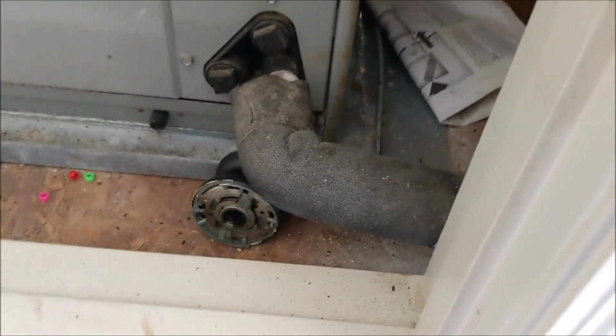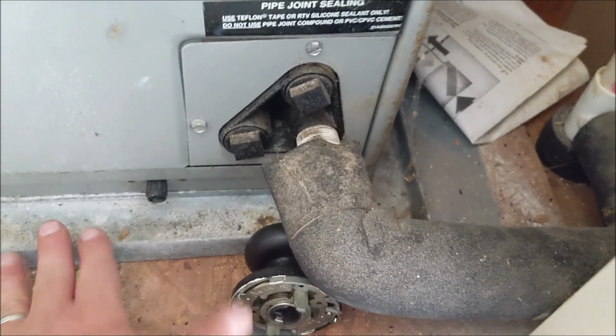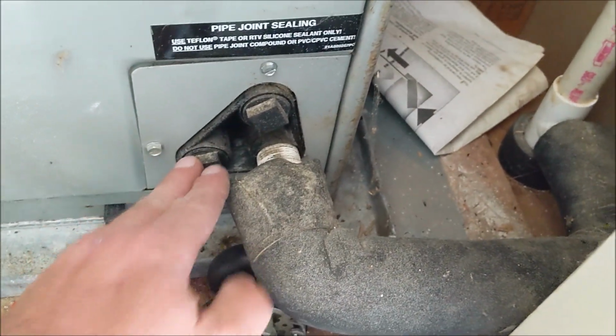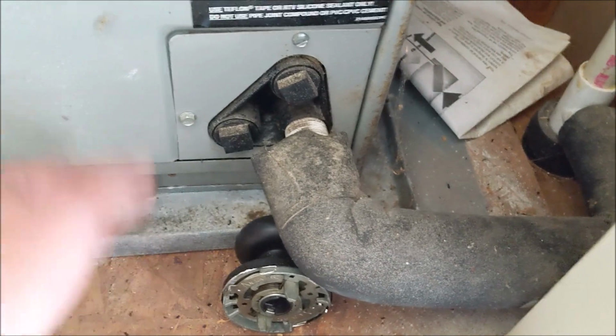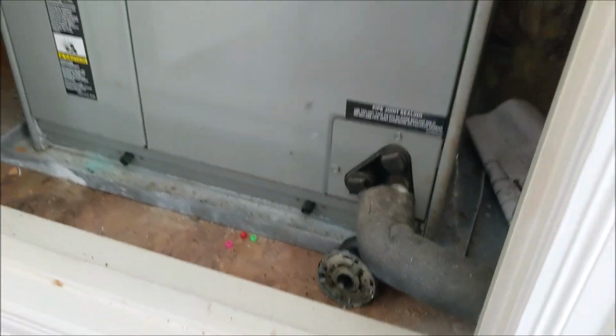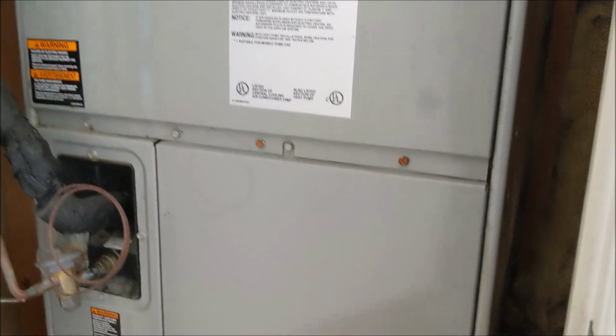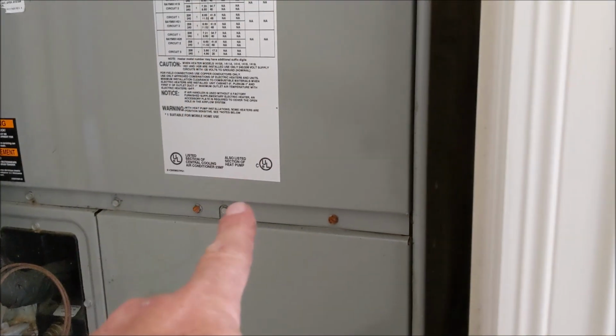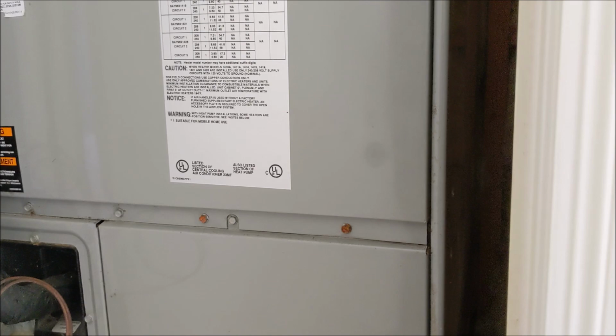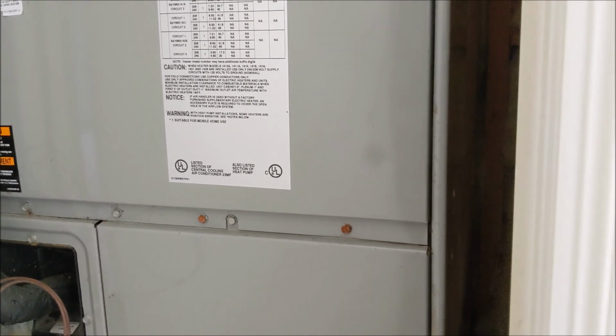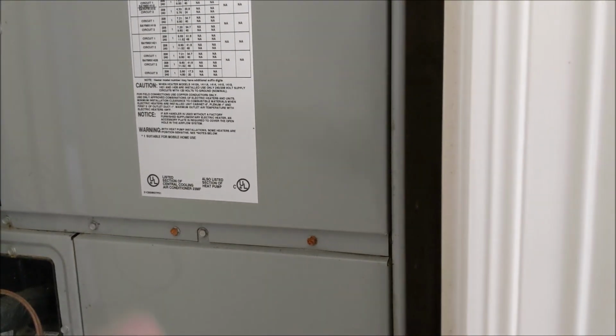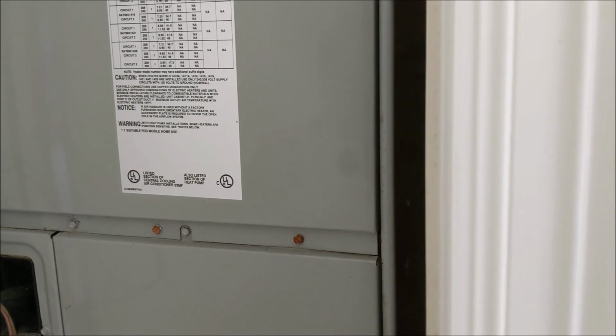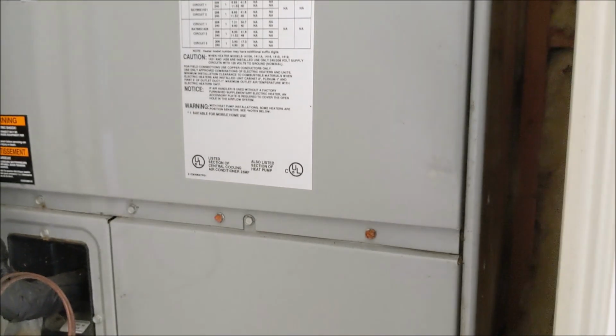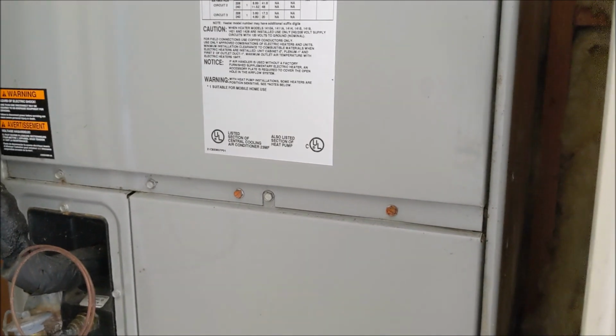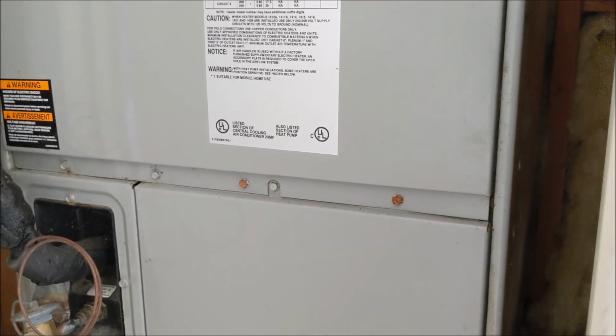So at the laundry room where the electric air handler is, we have an emergency drain pan, so a float switch is not required since we do have an emergency drain pan. Although we recommend it, but it's not required. So just have this electric air handling unit checked out. Like I said, I think it's going to be the capacitor. It's going to either be a 5, 7, or 10 microfarad capacitor that controls that blower. I tried changing out the capacitor, make sure that's fine, and you should be able to operate it, so the technician should be able to run the air condition and the heating.